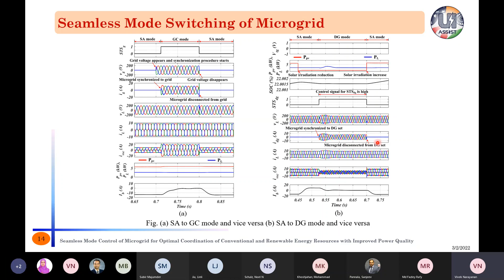Hence, the system tries to synchronize to the DG set. In the meanwhile, the battery will provide the load demand. And after satisfying all the synchronization conditions, the control pulse of the solid transfer switch at the DG set becomes high, and thereby the DG set gets synchronized into the microgrid, and then it provides power to the critical loads. Moreover, from 0.7 second, we can see that PV power has again increased such that it is sufficient to meet the load demand. Then the control pulse for the solid transfer switch automatically becomes low, causing the DG set to be disconnected from the microgrid, and the standalone mode control is applied to the voltage source converter.